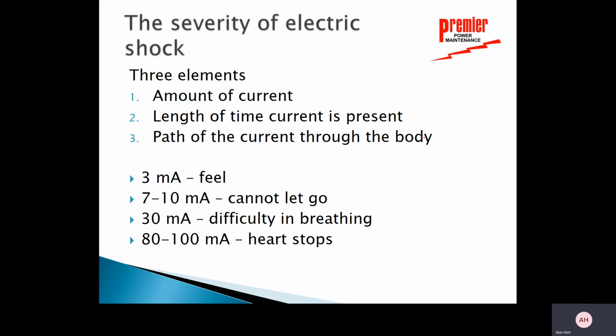So typically for us, in a substation generating plant type setting, we're thinking like 15 cycles or a quarter of a second. For all industrial settings, we're probably talking about 30 cycles for the fault itself. But if we have ground fault systems that are not properly installed, it may not trip at all. So looking at the history of that, we can understand that 3 milliamps of current, 3 thousandths of an amp, we can feel. Somewhere between 7 and 10 milliamps, 10 thousandths of an amp, I can no longer let go. 30 milliamps worth of current, and I can have real problems trying to breathe and catch my breath.